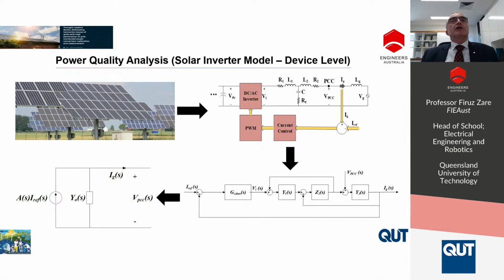This is one of the analyses that we did for solar inverters in terms of modeling. When we do an LCL filter, with different passive damping using a resistor, and when we design the controller GC in this block diagram, overall we can simplify a solar inverter as a current source, generating fundamental and harmonics depending on the transfer function. But the most important factor is that this current source is not an ideal current source. It has an input impedance, and the input impedance depends on many factors: control system, control parameters, and your LCL filter. And it has some resonances.